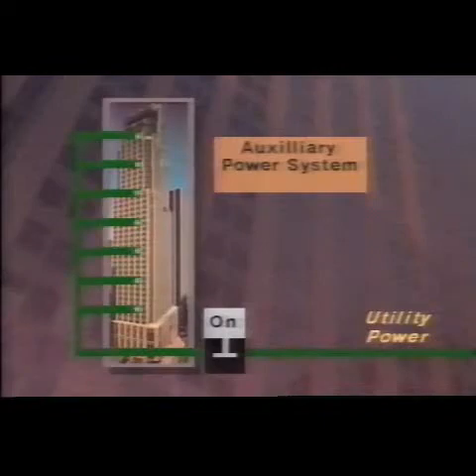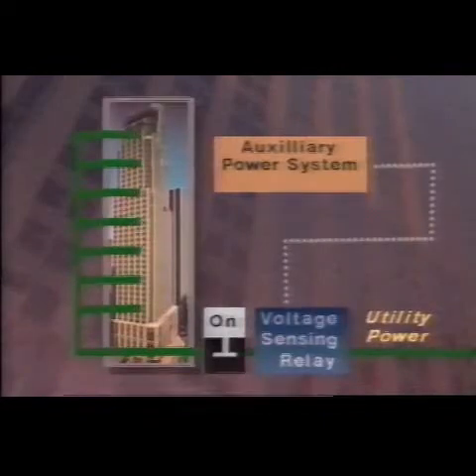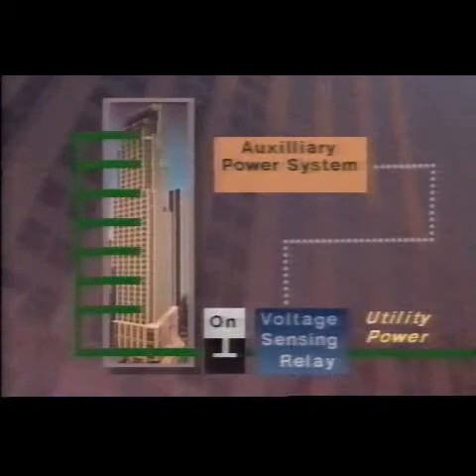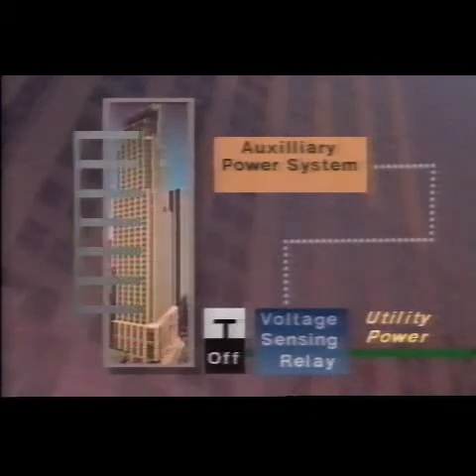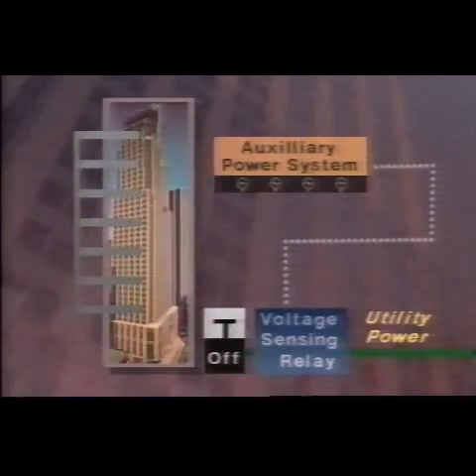Conceptually, the system looks like this. Utility company power coming from the street enters the building through a switch to the building's power bus riser. Each floor is powered off the bus riser, and the utility meters the power of each building tenant. As designed, the auxiliary system monitors the power as it enters the building through a voltage sensing relay. In case of a power interruption, or on occasions when the power company asks for relief during peak use, the system opens the switch connecting the building to external power and starts up the building's auxiliary system.